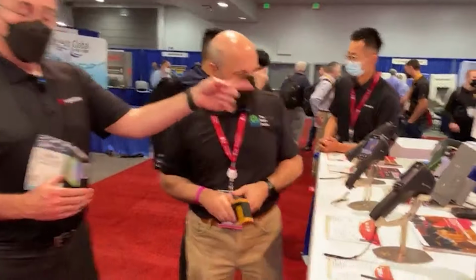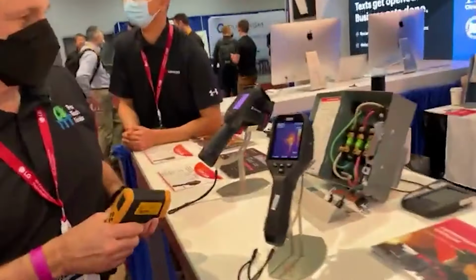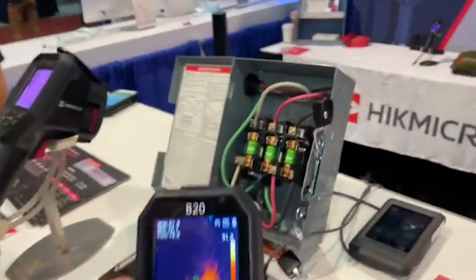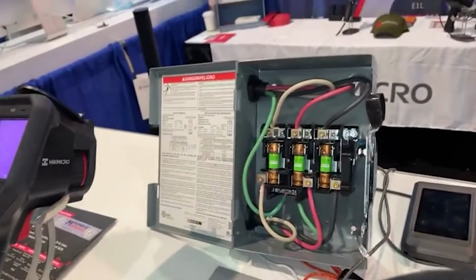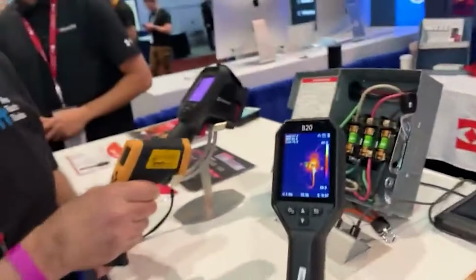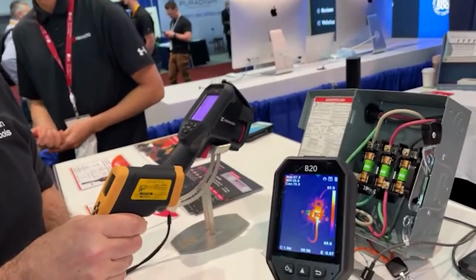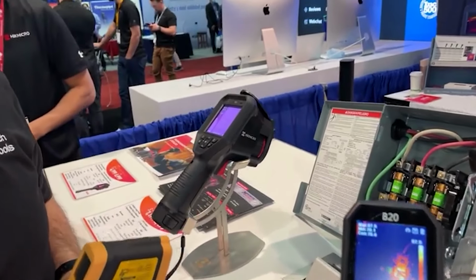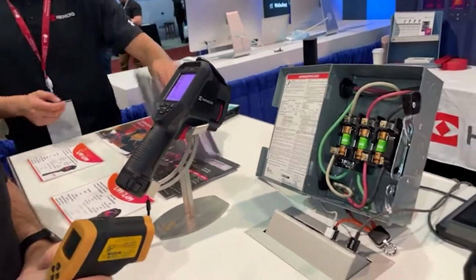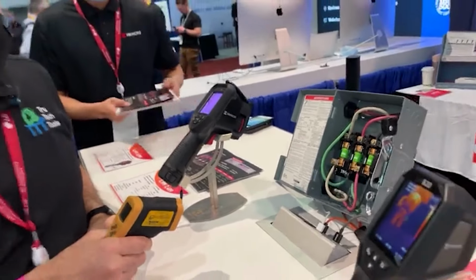So if we look at an electrical fault, we might be looking at something that's only a quarter of an inch. Well, how close do I need to be? I need to be right on top of it. And with a fault inside of there, with the IR thermometer, I've got to check every single potential connection.